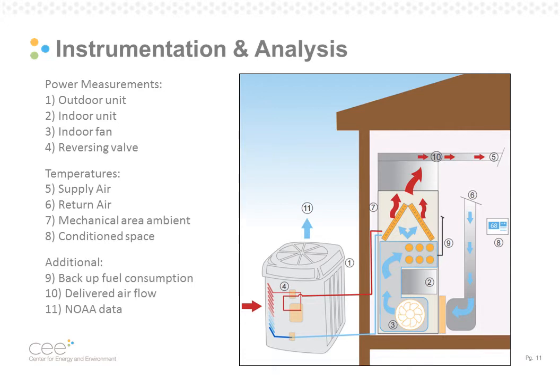Each home was instrumented with a residential HVAC data acquisition system. We're using a Campbell logger at each site to collect data at 1-second intervals. So you can see we're taking power measurements of both the indoor and outdoor units, and we're also submetering the indoor fan. We're monitoring the reversing valve so we know when the unit runs in defrost mode.